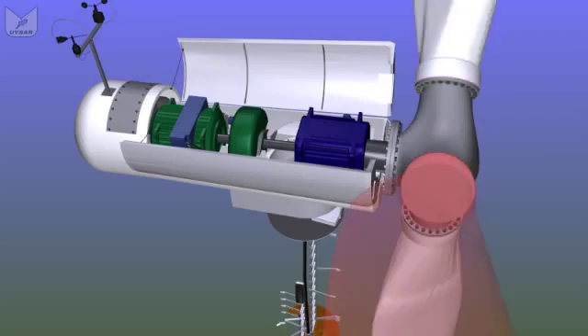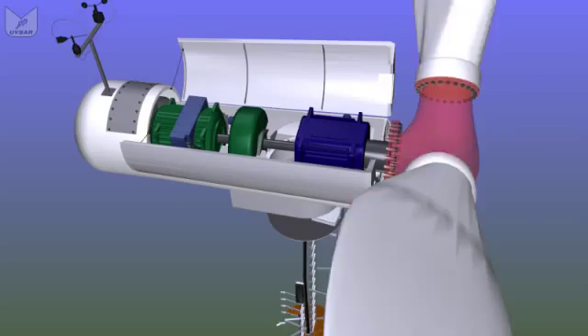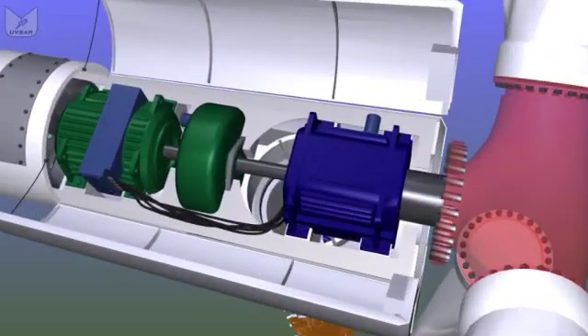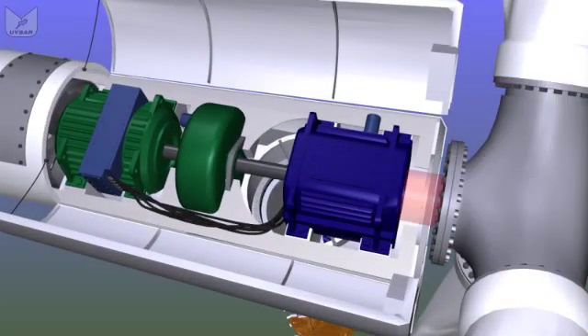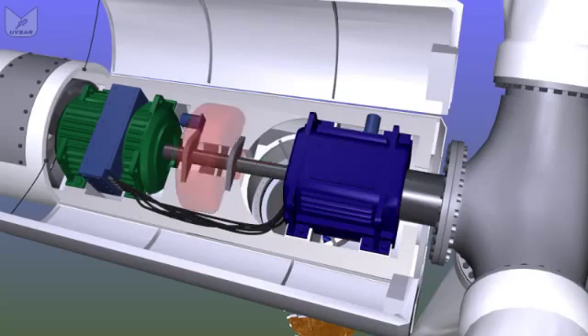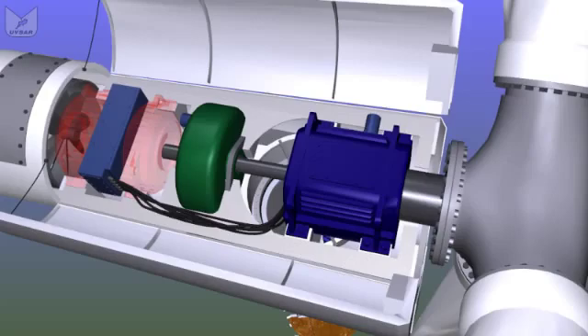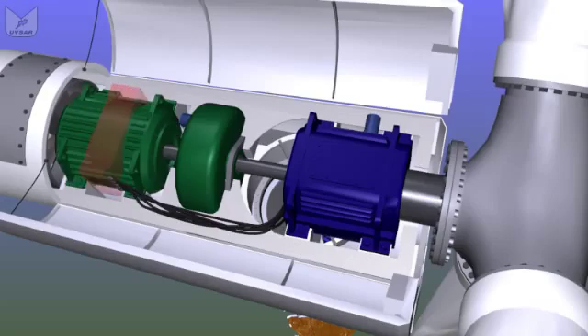And the blades can turn or pitch, so that the angle they form with the wind can be varied. Out of the back of the hub, we have a shaft, which leads into the gearbox, then a high-speed shaft, through a brake, into a generator. And that generator then supplies the electrical power, as I say, at about 690 volts, all the way back down the tower to the base.